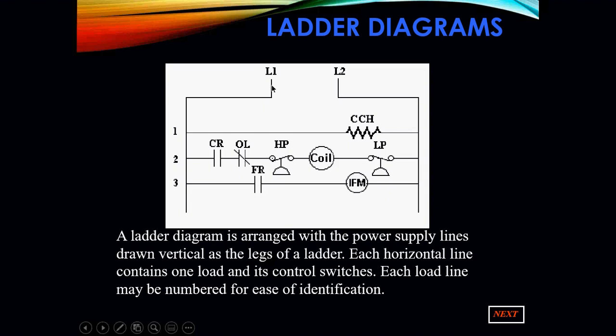That's where we begin our troubleshooting on any particular piece of equipment. Do I have power between L1 and L2? If this is like a 208-230 type application, or if it's L1 and neutral, if it's a 120 volt application, if we make sure that we have power going across here, we should be having power across each one of our branches, hence the name ladder diagram. You could always think of the sides as the sides of the ladder.